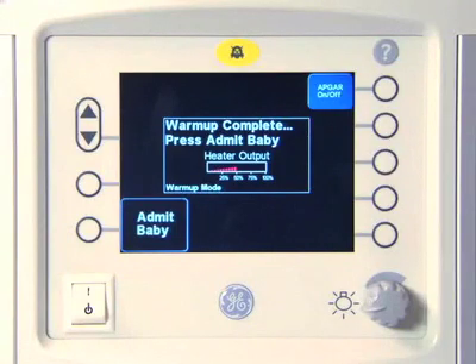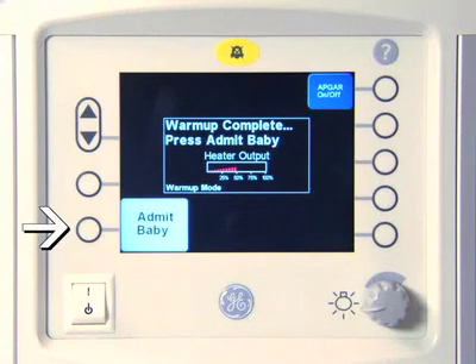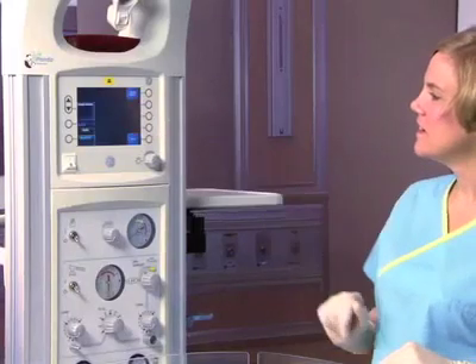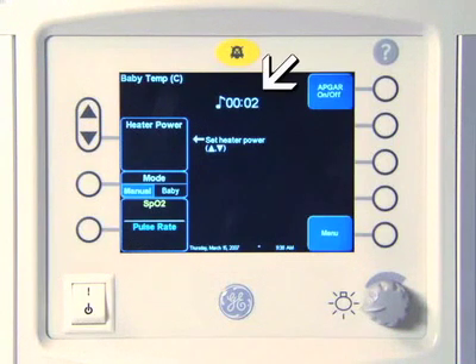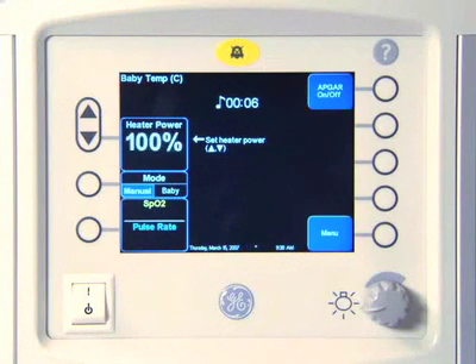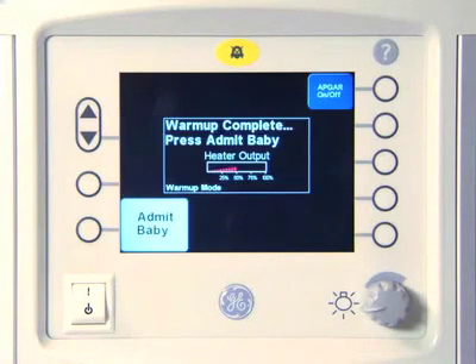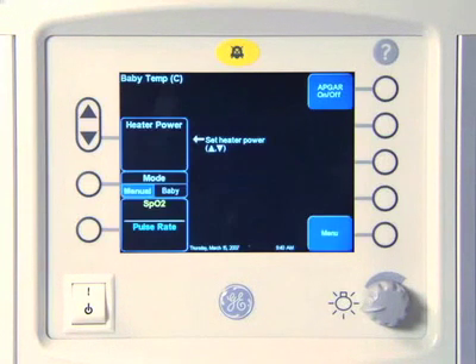To stop warm-up mode and begin normal operation of the PandaWarmer, you can press either the Admit Baby key or the APGAR On-Off key. Pressing the APGAR On-Off key starts an automatic timer. The PandaWarmer begins normal operation in manual mode at 100% power. We'll discuss the APGAR function in a later section. Pressing the Admit Baby key brings the PandaWarmer to normal operation in manual mode at 100% power.